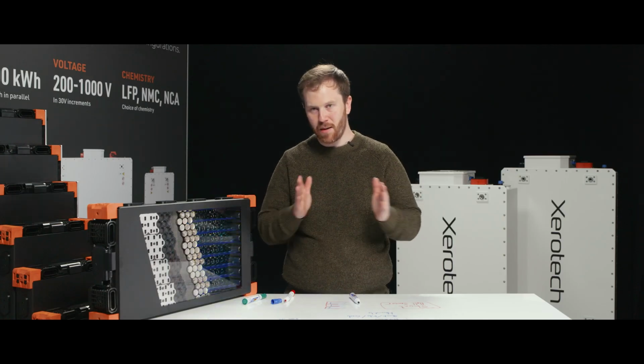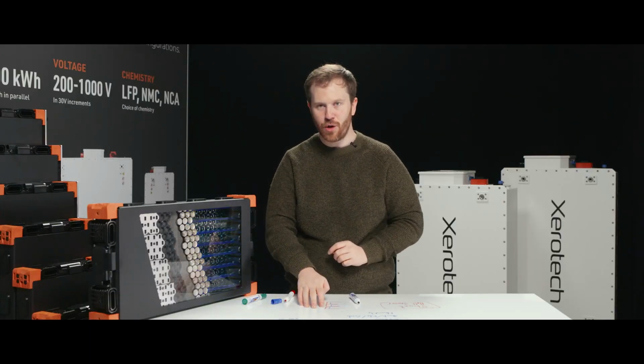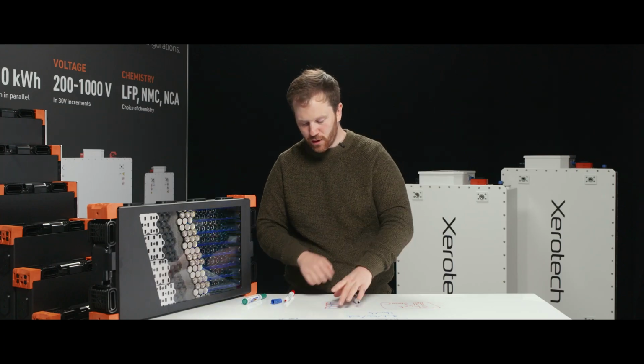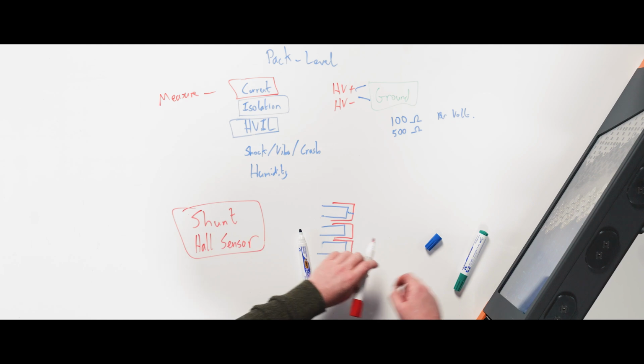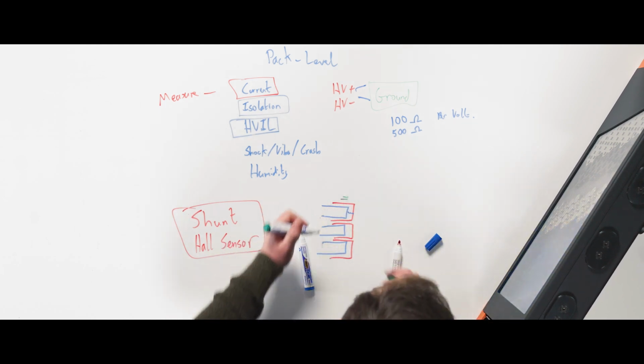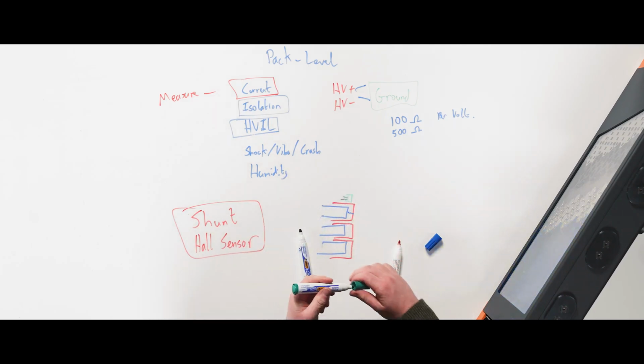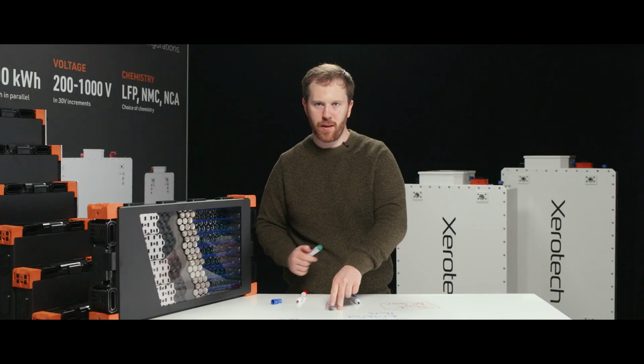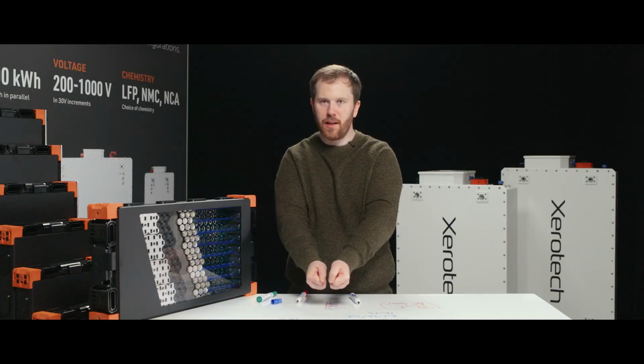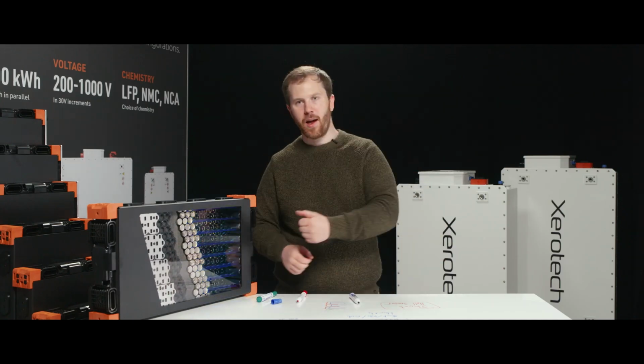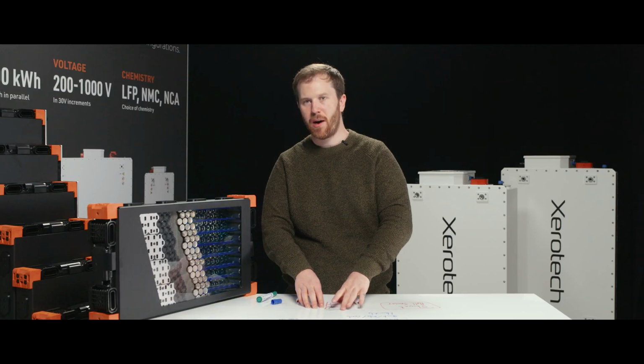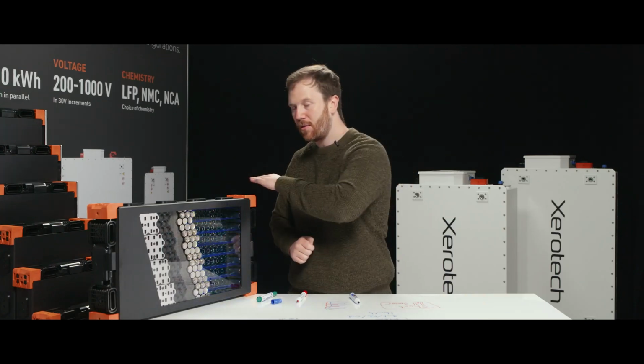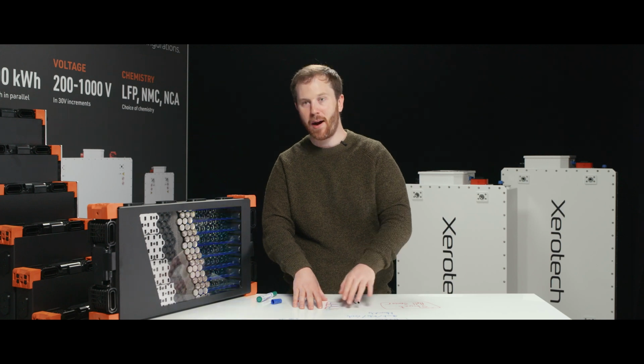Or worse yet, it's not really on making, but mainly breaking the current. It could spark and then hold a plasma and actually hold a much larger gap, which is incredibly destructive and damaging to the contacts and can also present a fire risk. So with a connector design like this, they actually have a separate little sensor circuit, a little set of pins that go into another socket here. And these will be break first and make last pins. So that means that this will open slightly and it will send a signal to the controller that the connector has been opened, but it's still electrically connected with the main power connectors. This sends a signal back to the BMS, which instantly opens the contactors or tells the system to stop drawing load to ensure we don't create an arc flash in our connectors.